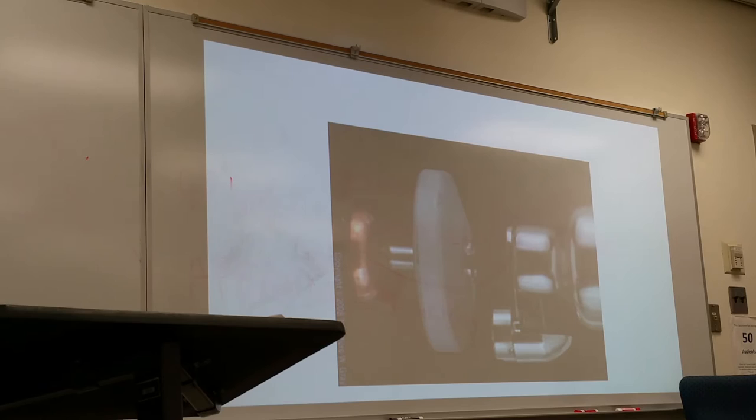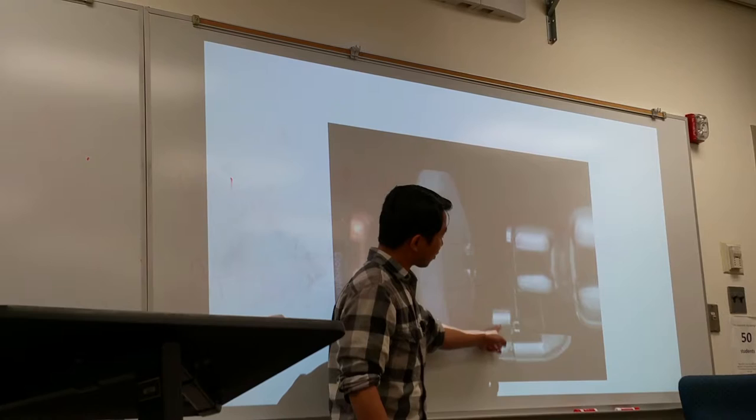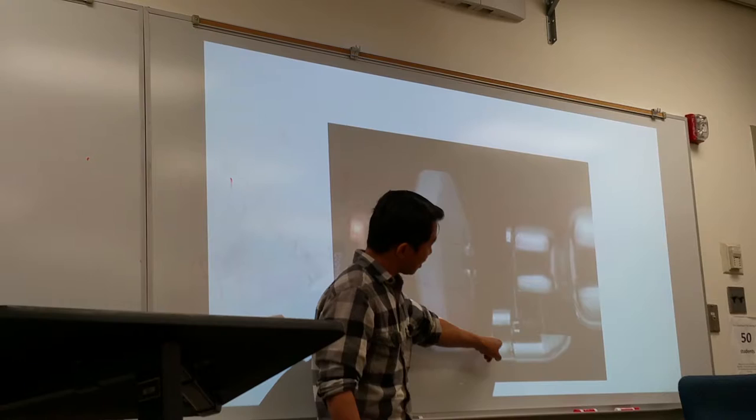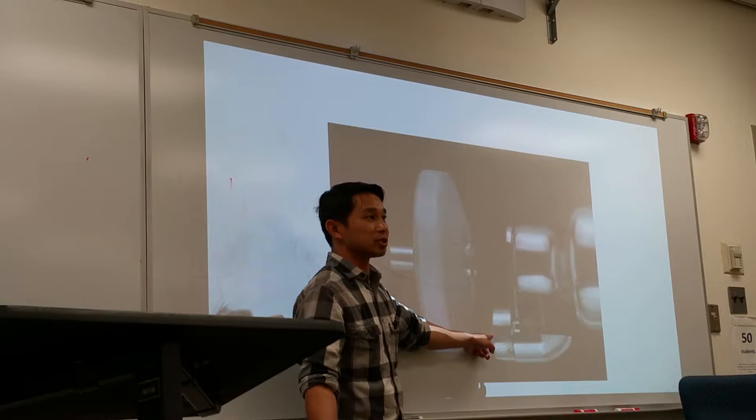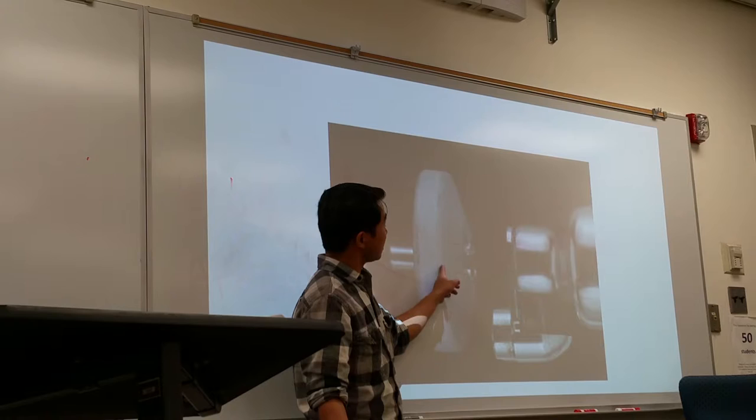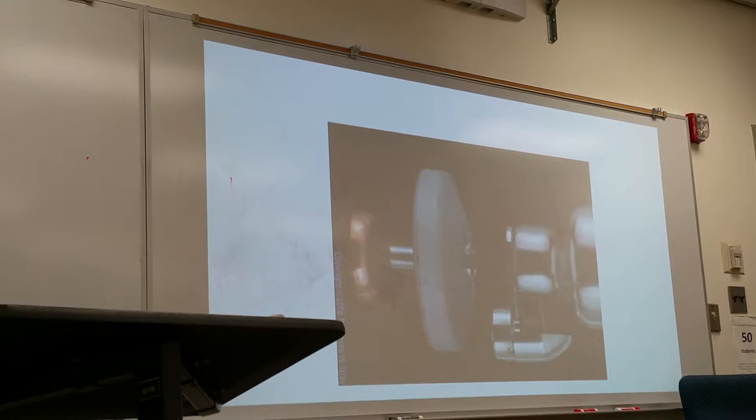Here is a picture of the cathode and anode. The filament is within the focusing cup, very close to the anode side, which mainly has a large tungsten disk. Electrons coming out from the cathode side through thermionic emission travel at very rapid speed and interact at the anode side — they strike the disk, and the electron interaction with the tungsten disk produces x-ray photons.